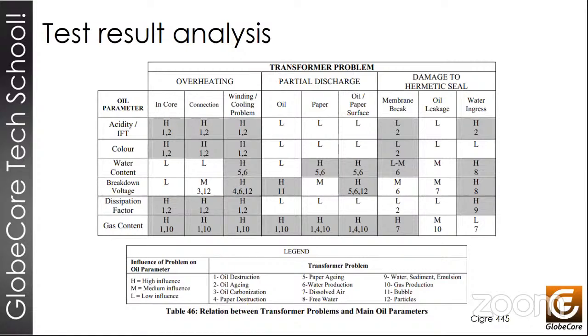We can learn a lot from this information, and this is a very important analysis tool. We are usually focused on seeing whether it passes or fails within the limit of the test being performed. Now we have to do the test in the field and see what they tell us. So with this matrix, we can see a lot of information about what the test does, and we can directly relate it to different problems inside the transformer, and we can know the location of the problem much better. And when we have evidence of a problem and know where it is, it's natural to take corrective action.